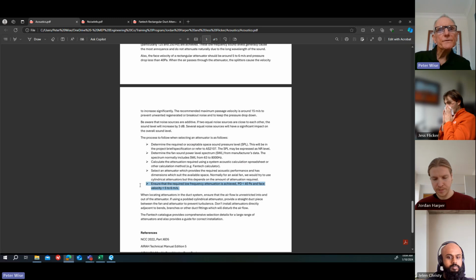And when we're talking about rectangular attenuators, ensure that the required low frequency attenuation is achieved. Pressure drops less than 40 pascals and face velocity is around 5 to 6 meters a second. If you're using an attenuator which has got quite wide airway width, in other words, you're not looking for huge attenuation, then you can probably increase the face velocity. You can use your judgment there.